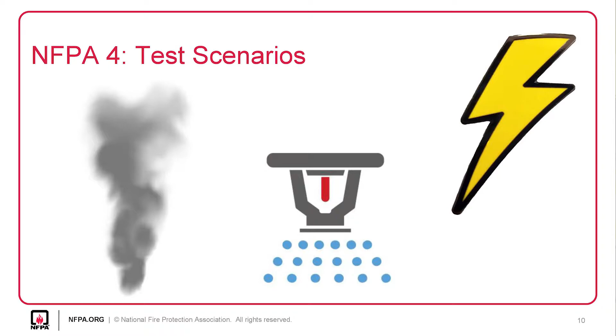And then the other one is the loss of power. One of the biggest things within integrated testing is that most life safety systems are required to be provided with emergency power. So you need to test all of these systems. Not only do you need to test the integration under normal power, but you now need to test all these systems under emergency power, so you need to test for the loss of power.